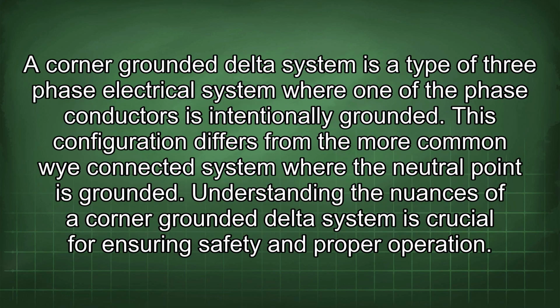A corner-grounded delta system is a type of three-phase electrical system where one of the phase conductors is intentionally grounded. This configuration differs from the more common Y-connected system where the neutral point is grounded. Understanding the nuances of a corner-grounded delta system is crucial for ensuring safety and proper operation.